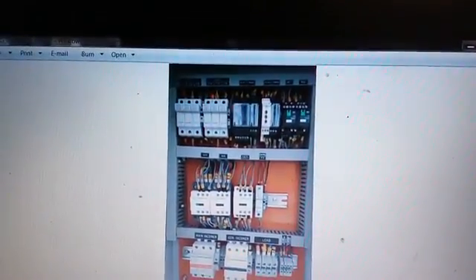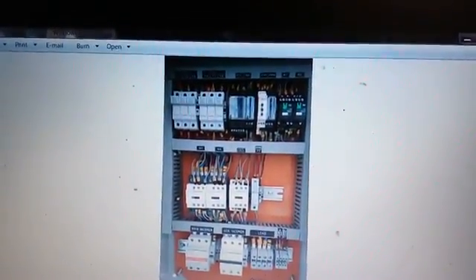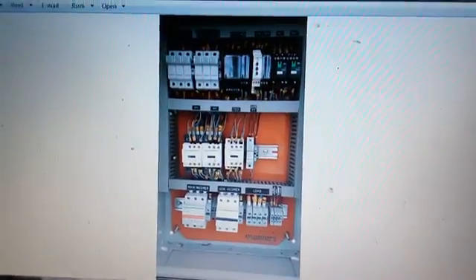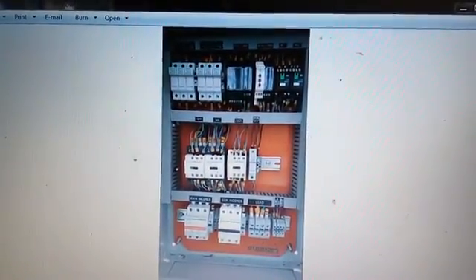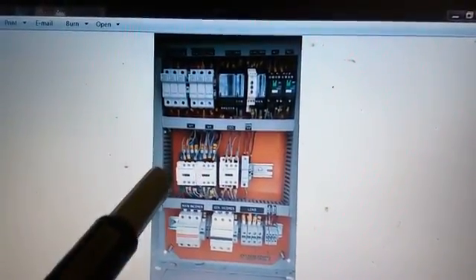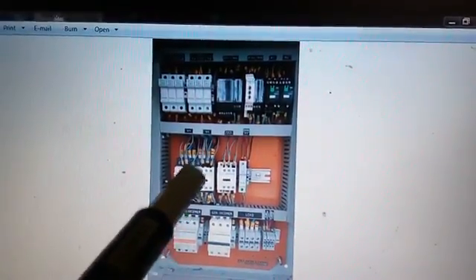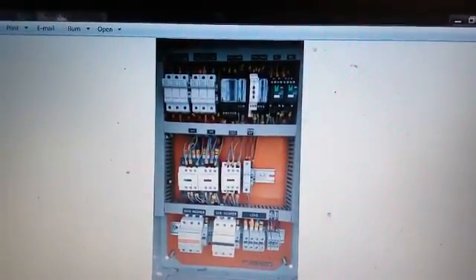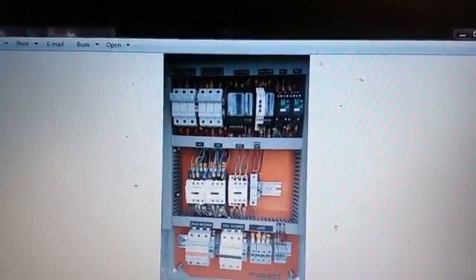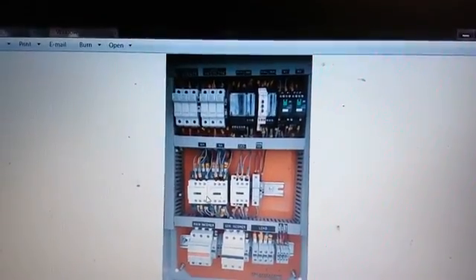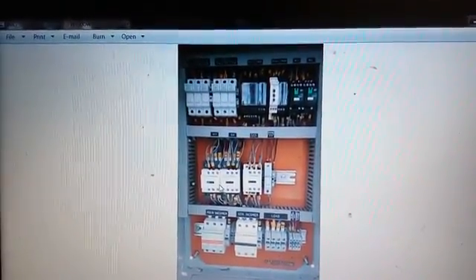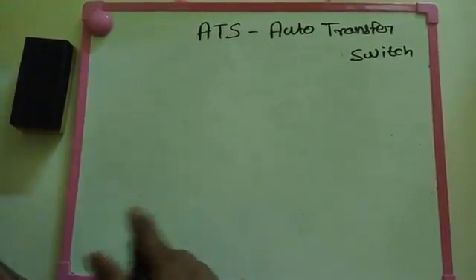So this is the outside of the ATS panel for a simple ATS panel - this is a very small ATS panel. If we make a big ATS panel, we need to put a voltmeter, an ammeter, and other things. This is for the interlocked contactor, that means only one supply at a time will be operated - mechanically interlocked inside. That's all. After that we'll see how to connect the ATS panel.